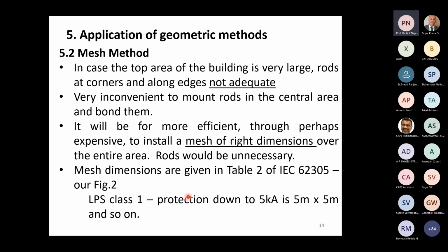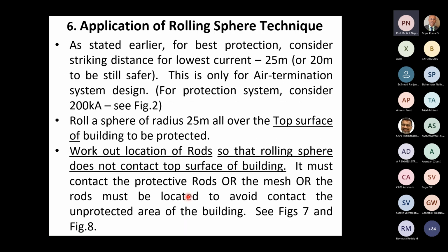Therefore, what is done commonly is, on top of this building, on this broad area, we provide a mesh made up of copper strips having a spacing of, for example, 5 meters by 5 meters. If you want to have a higher degree of protection, 10 meters by 10 meters for a different degree of protection, like that. So this is the mesh method. I'll come back to this a little later.